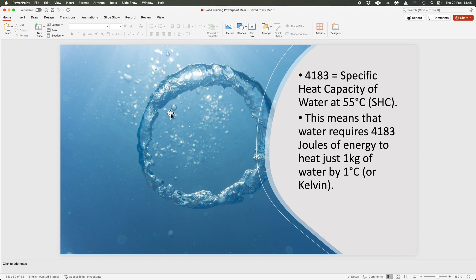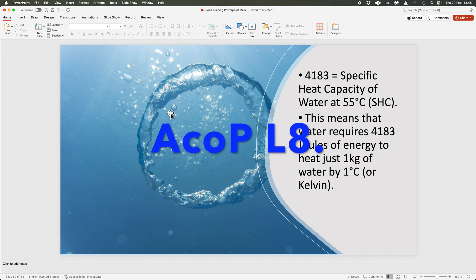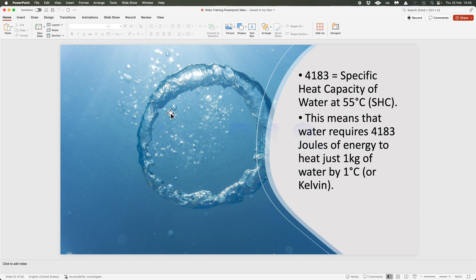What we want to do is get efficiency right up to around 92–93%. This is why lower temperatures are so important when you're designing — this is why 55 degrees was deemed the correct maximum flow temperature. On combi boilers and similar systems, try to get it down to that level. If you've got a priority hot water setup, that should automatically ramp the temperature up so you can do pasteurisation cleansing once a week to comply with AcoP L8, which is legionella protection on hot water cylinders. That applies to stored water; instantaneous water doesn't fall under AcoP L8.